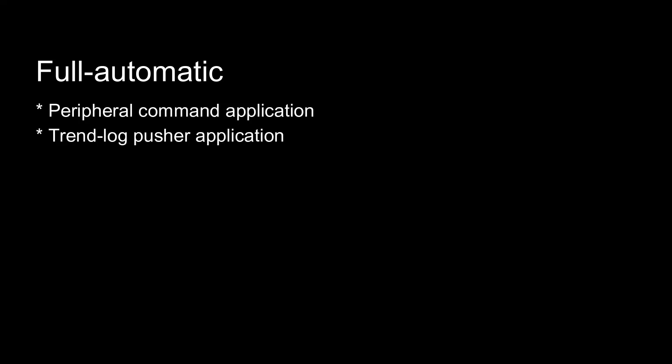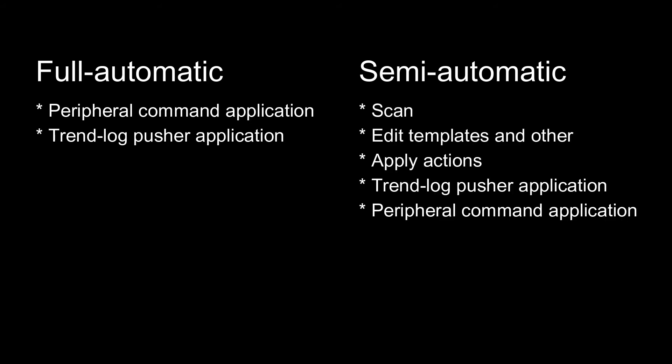To summarize, we can do a fully automatic configuration of the mBus by only using the peripheral command application and the trend log pusher application. Or we can do a semi-automatic configuration by using scanning, edit templates and other things, apply actions, and using the trend log pusher application. The peripheral command application can then also be activated to automatically configure any later attachments of mBus meters.